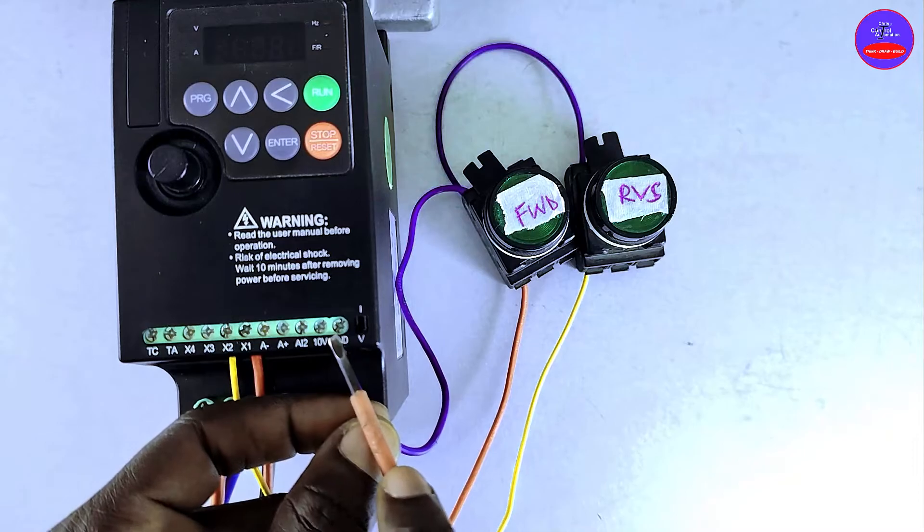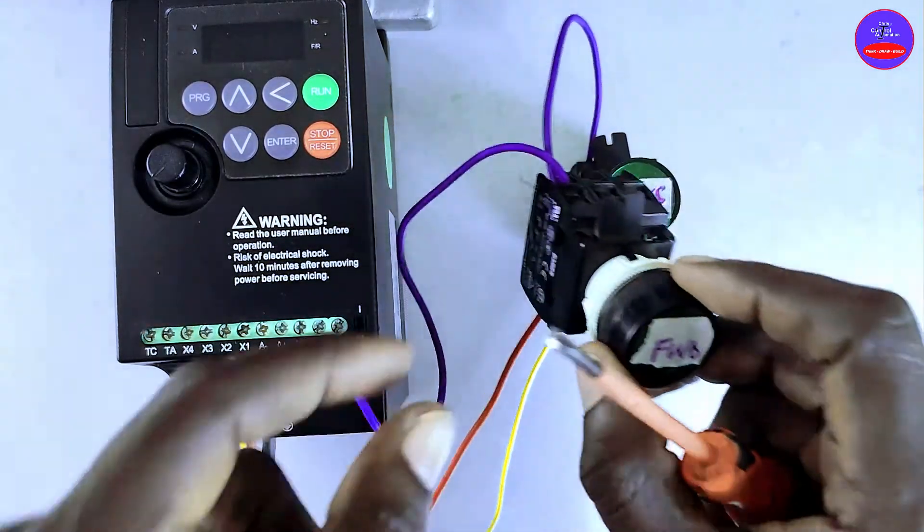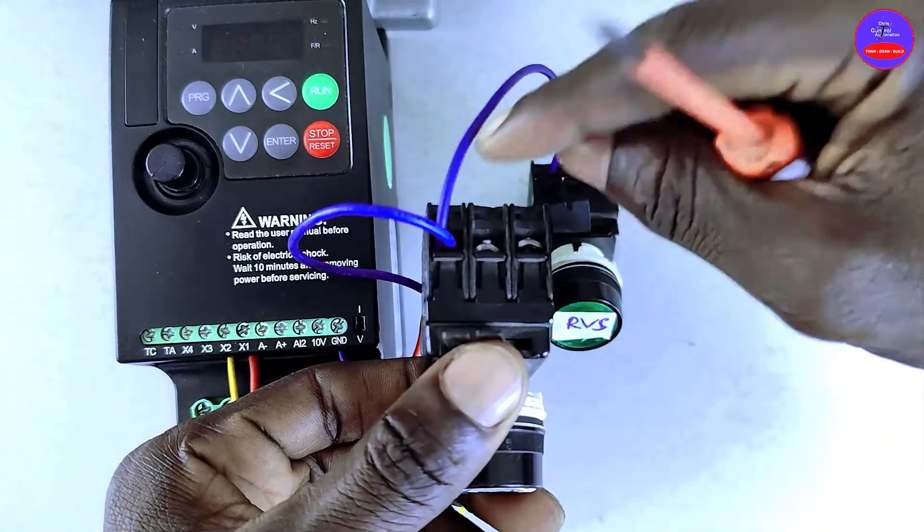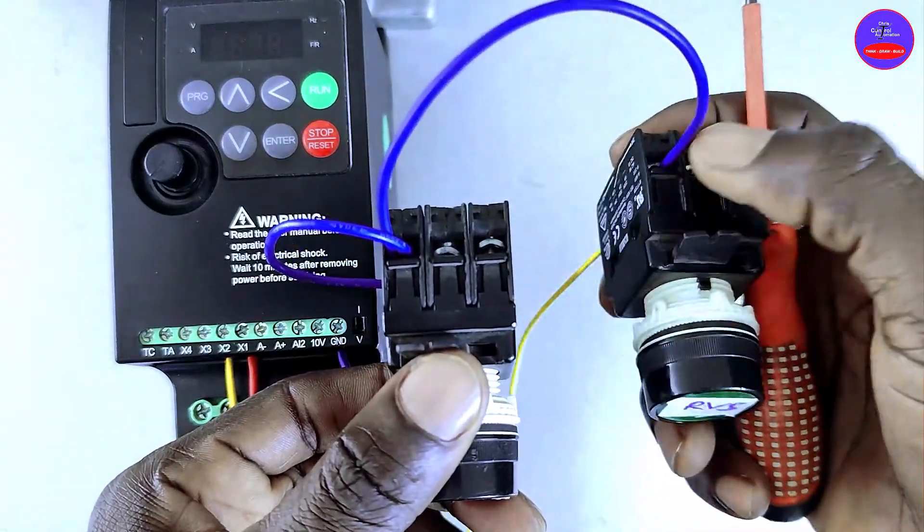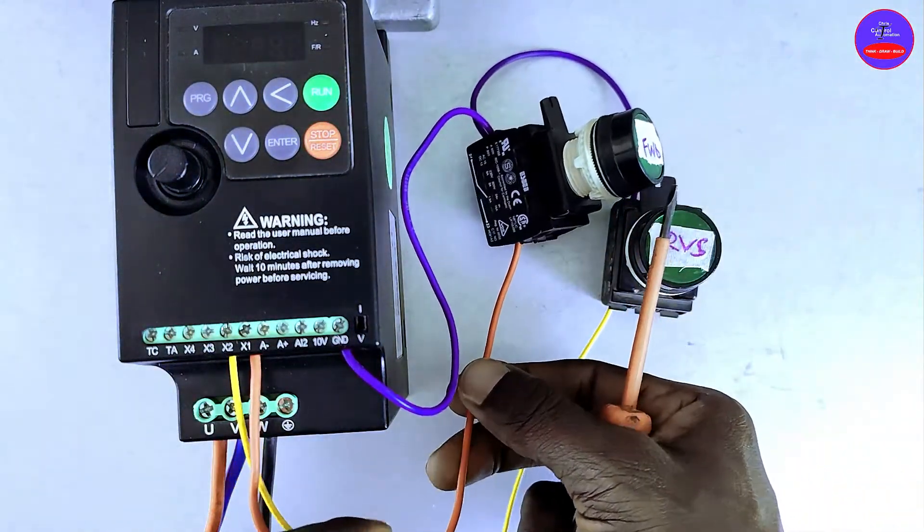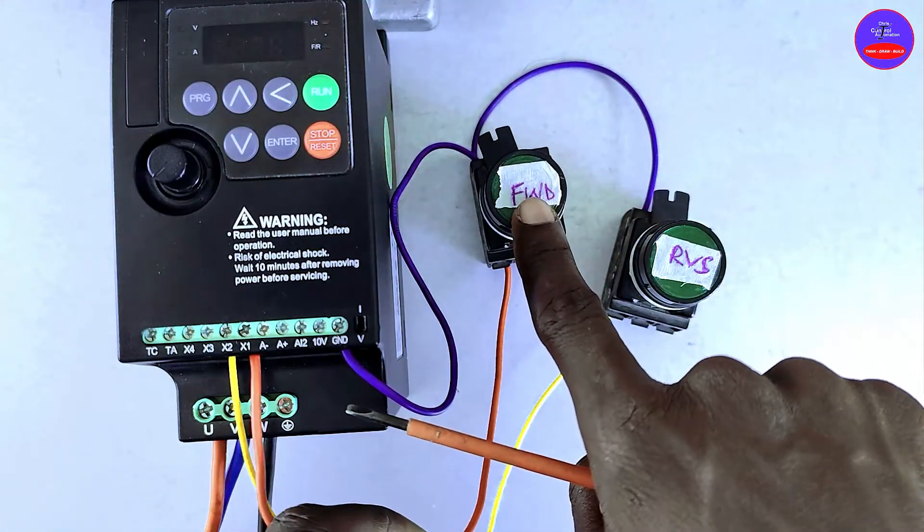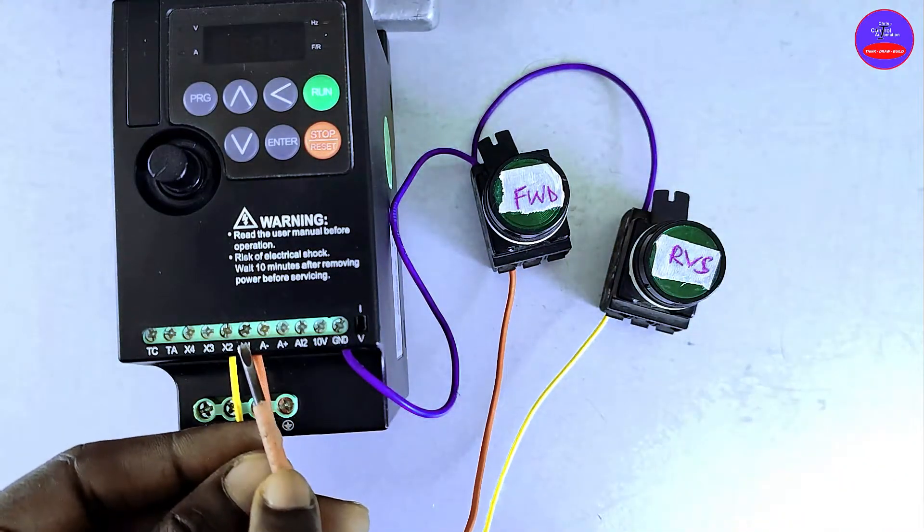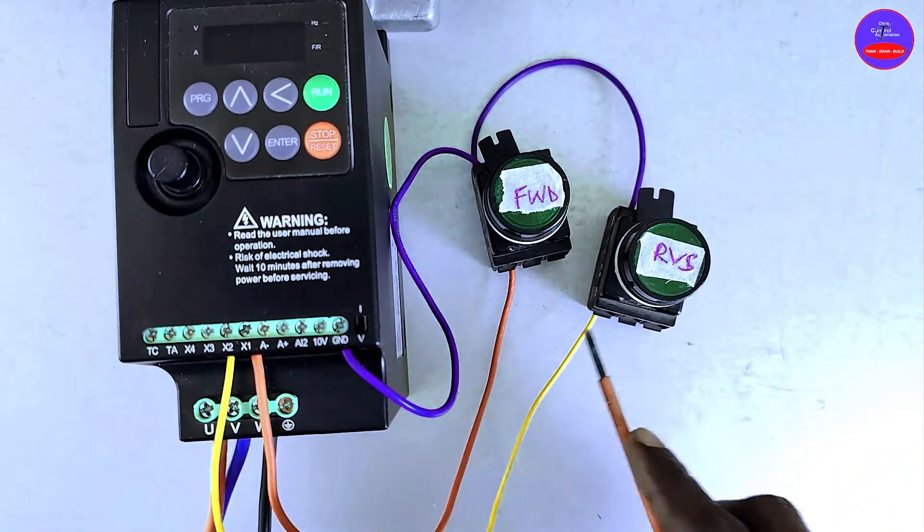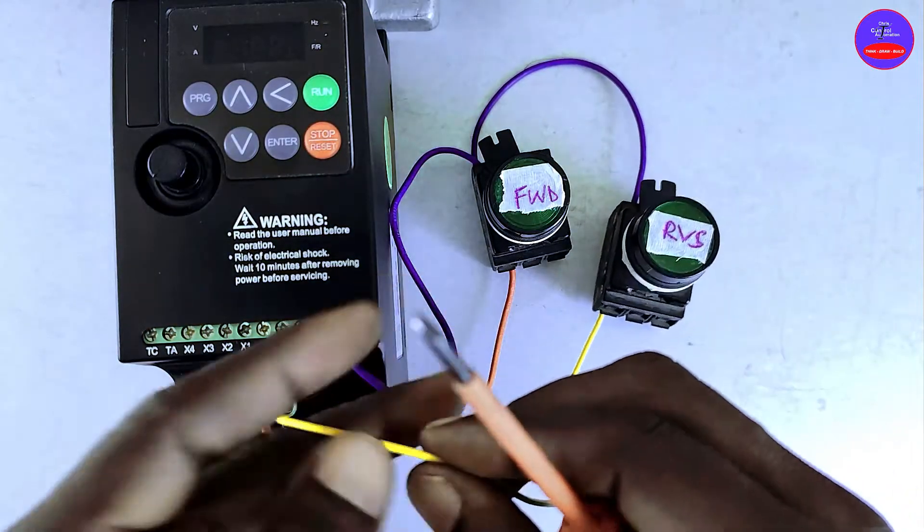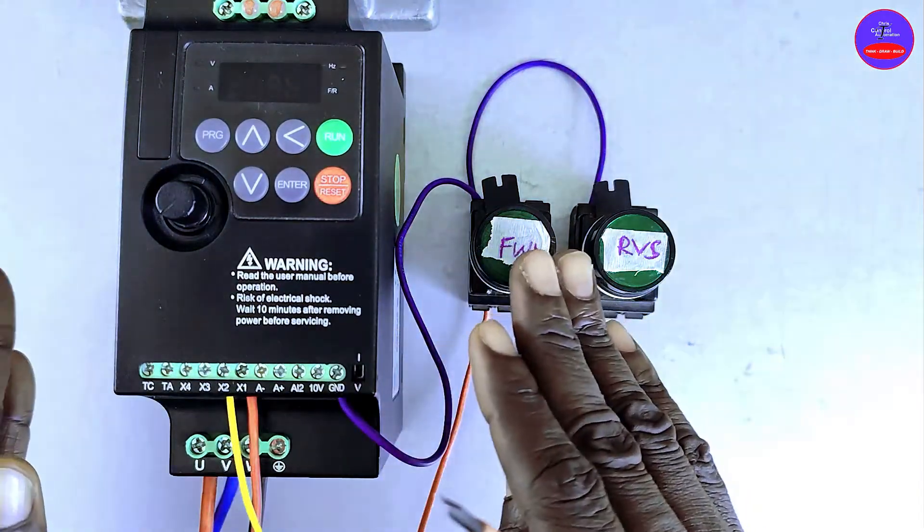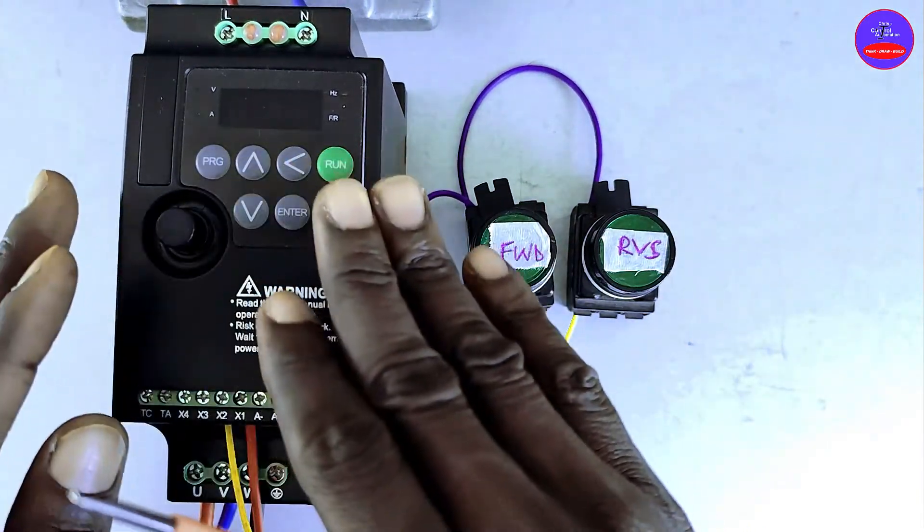We tap from the negative terminal on the drive to one side of the forward push button. We tap from the same place to one side of the reverse push button. The red cable comes from the other side of the forward push button and connects at X1 terminal. The yellow cable comes from the other side of the reverse push button and connects at terminal X2. This is the connection. Let's run the drive and program it.